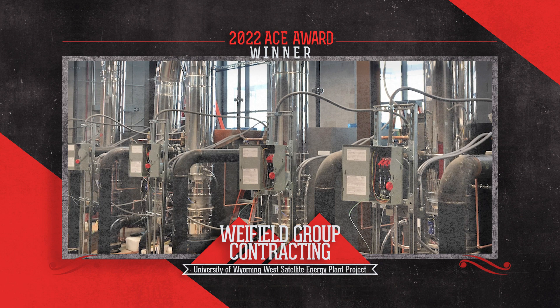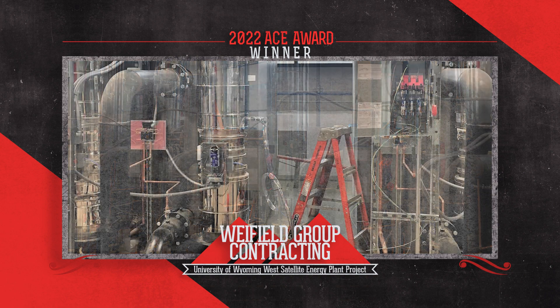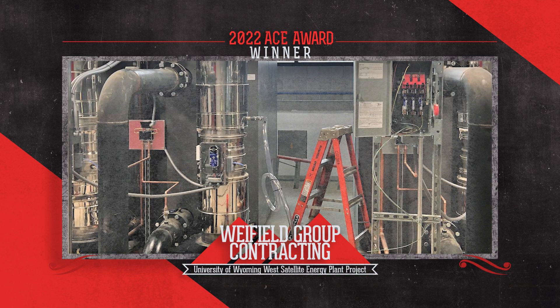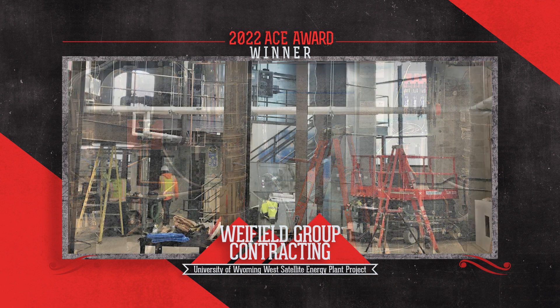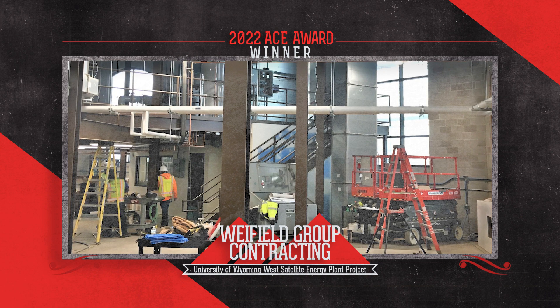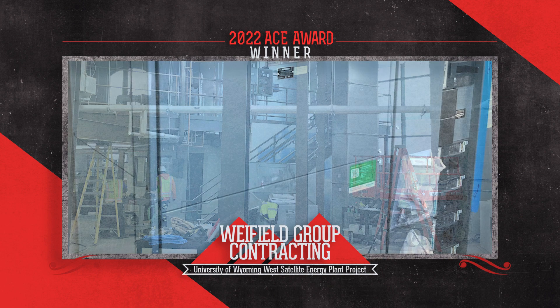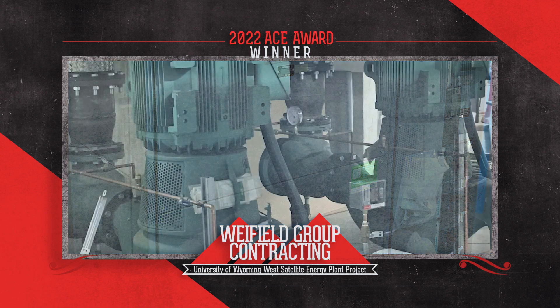The campus's hot water system would also originate from the same new plant. This new unmanned West Campus Satellite Energy Plant would be remotely monitored from the main central energy plant in Laramie, Wyoming, where the steam originates, and is comprised of a new 13,700-square-foot facility with two primary levels and a utility platform to house mechanical equipment. It also included a new 13.8 kV medium voltage service entrance, electrical distribution, fire alarm, and first responder radio amplification, as well as technology systems to serve the campus hot and chilled water infrastructure distribution network.